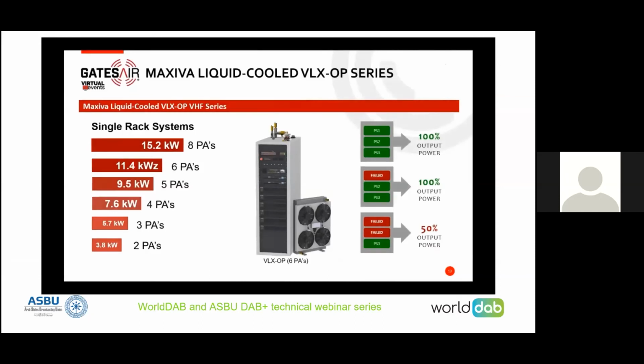In these contemporary designs, a full cabinet can be very power dense—nearly 15.5 kilowatts is the power level available in one rack, down to a couple of kilowatts. The modules are all hot pluggable and removable, going to a common heat exchanger and pumps.